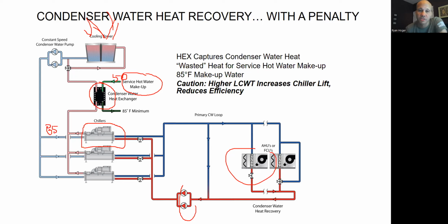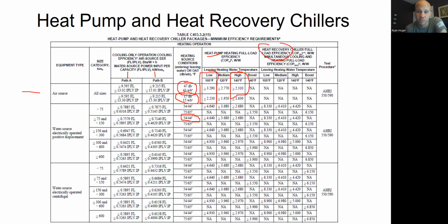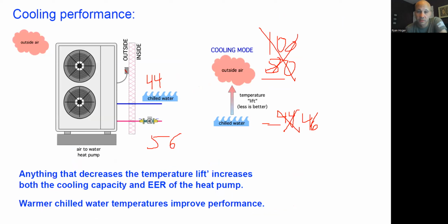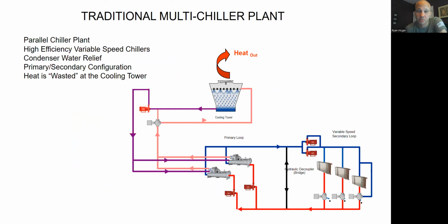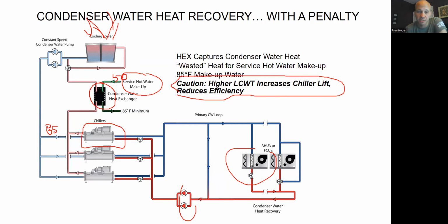The heat exchanger captures the condenser water heat, which is waste heat, as we said, from the 85-degree water. But this is where I was going with it. The higher leaving water temperature that I'm trying to make with this guy is going to be increasing the chiller lift, and that reduces the efficiency. Remember, the lift was the difference between the water temp and the outdoor air, right? If I'm trying to make warmer water, this is going to penalize my lift, which penalizes my efficiency. So I do save energy compared to doing nothing, but I don't save all of the energy, just straight up, as if I thought I was going to save.